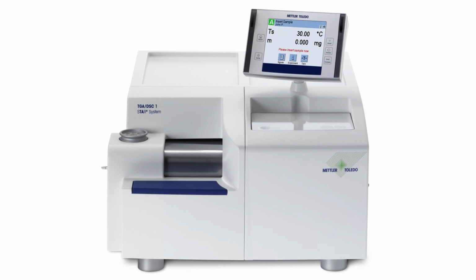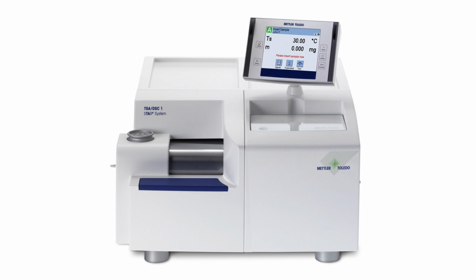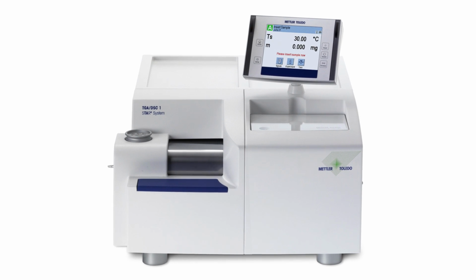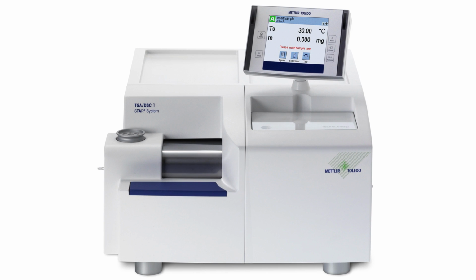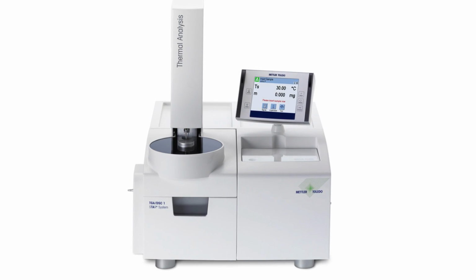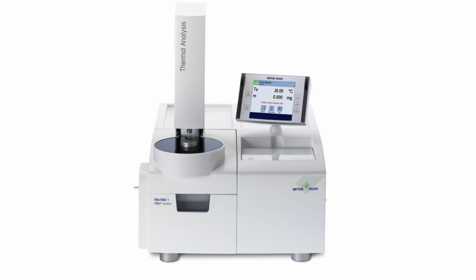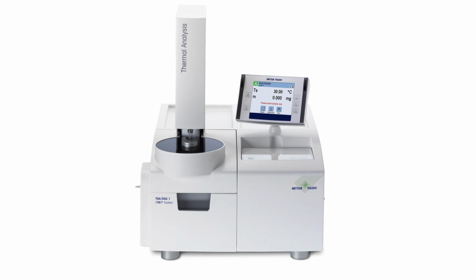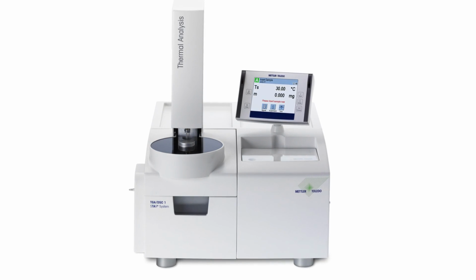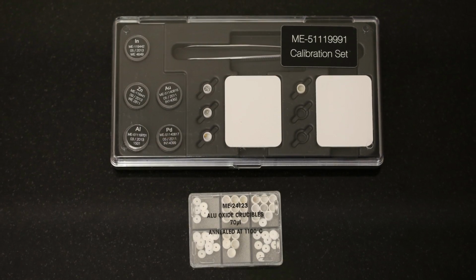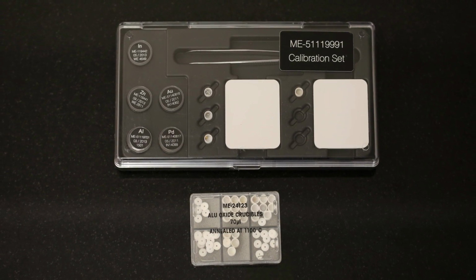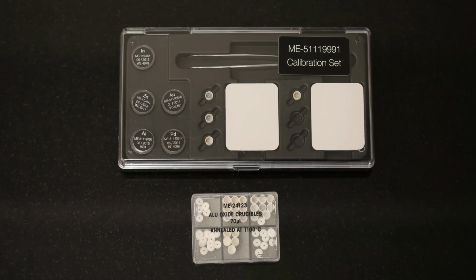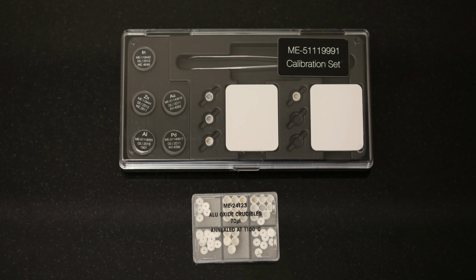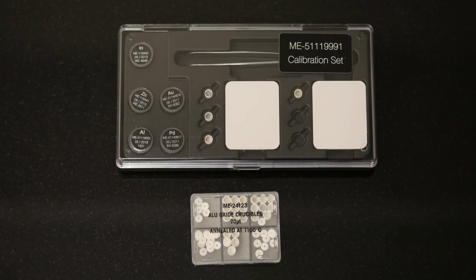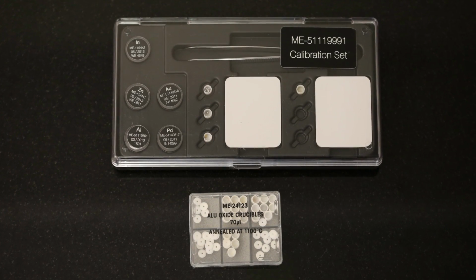TGA-DSC standard calibration. In order to achieve accurate results, a TGA-DSC has to be regularly calibrated and, if necessary, adjusted. We will now show you how to perform a standard calibration on a TGA-DSC using aluminum reference substance as an example. For a TGA-DSC standard calibration, you will need the following accessories: two standard 70 microliter alumina crucibles, the calibration kit, and suitable calibration material.